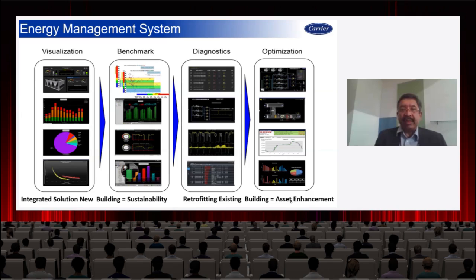Beyond this, it helps with diagnostics. The key performance indicators we get are expected to operate within a certain range. This data gives us signals that can be used as alarms when a performance indicator goes beyond range, so it alerts us, allowing us to correct issues ahead of troubleshooting after a fault occurs. We can preempt faults based on these indicator alarms, which helps optimize the system at the efficiency, operations, and maintenance levels.